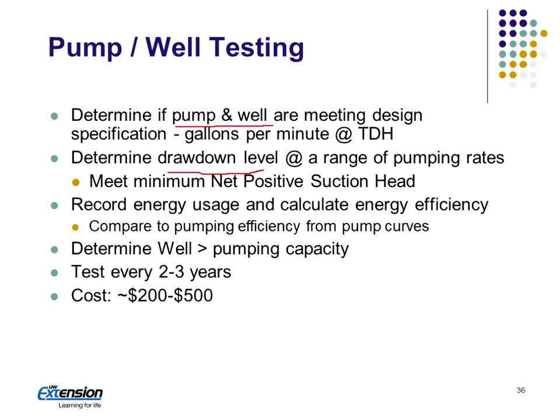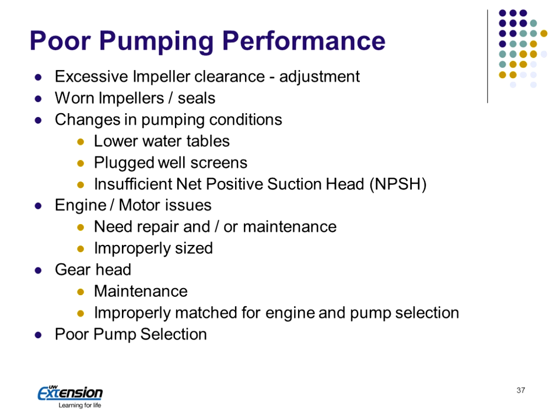The other thing you do is look at drawdown, to make sure that we meet our net positive suction head pressure, and we can record the energy use during this test, calculate the energy efficiency and compare it to the pump curves to see where we're sitting. Ideally, we should do this test every 2 to 3 years, and it's not real expensive. I look at it as cheap insurance because pumps never quit when they're not needed. So I think it's a good expenditure of money every couple of years, especially if you're doing lots of irrigation.